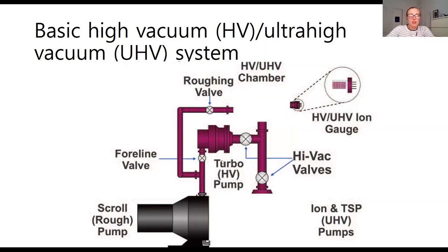Then use your high vacuum or ultra high vacuum pumps, which we'll go over different examples. You can open those up to your chamber. So it's always done in series where you're slowly bringing the pressure down to what you need for ultra high vacuum.